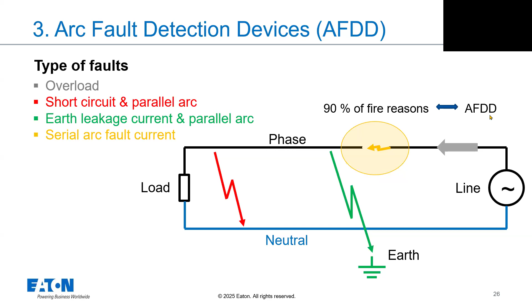And why do we speak about it? Statistically, when we take fires where an arc was the origin of the fire, 90% of fire causes from arcs are serial arcs. Then from the opposite side, we can say only 10% of arc faults are, let's say, in installations where they can be detected by an RCD. 90% must be, let's say, on the side of the AFDD. And now some overview.